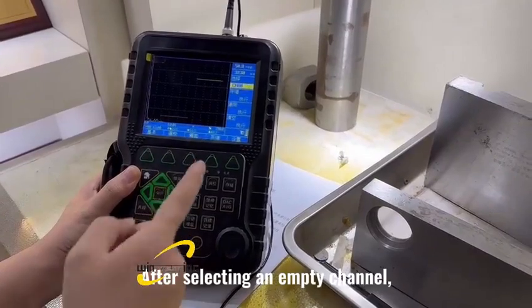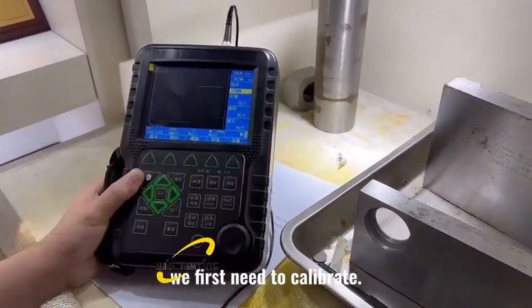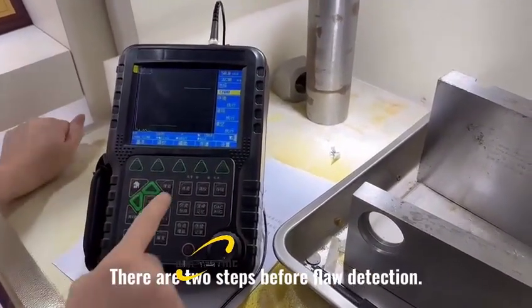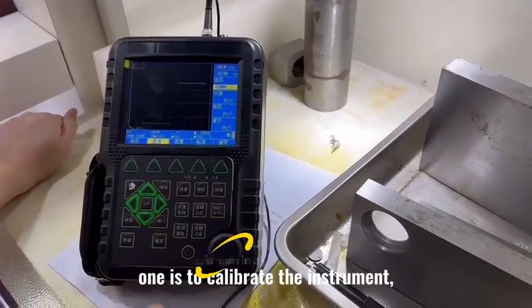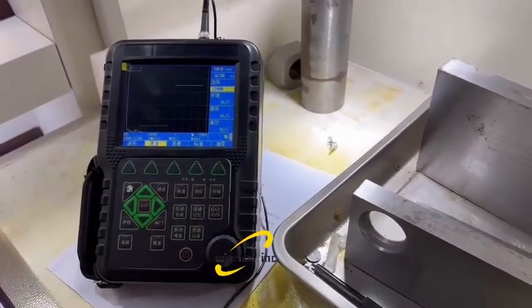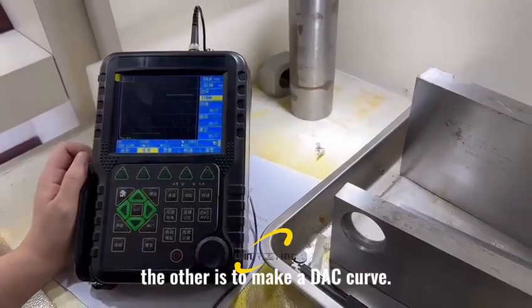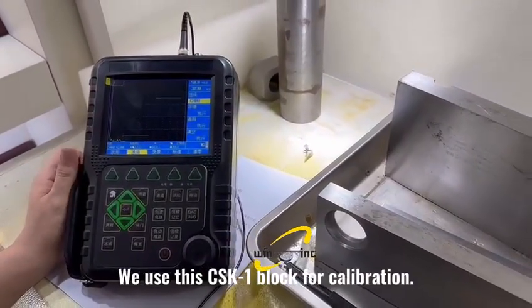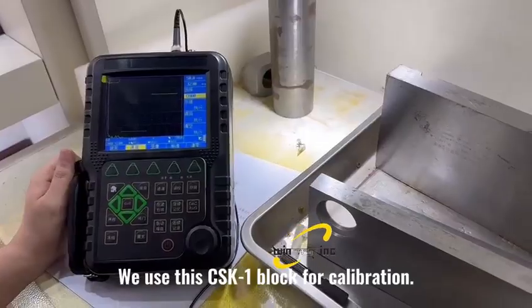After selecting an empty channel, we first need to calibrate. There are 2 steps before flaw detection. One is to calibrate the instrument. The other is to make a DAC curve. We use this CSK1 block for calibration.